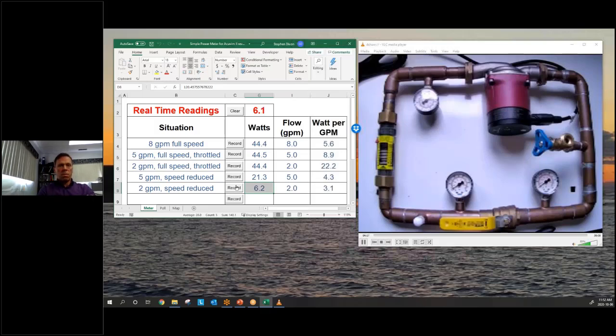Now, if you need pressure, we have to be careful here. If we need pressure, we may not be able to go that low. So in an open system where pressure is required, or if we have valves in the system, we have to be a little careful that we don't drop below it. There are going to be limits to how much we can reduce speed, because the throttling in the system may be a result of zone valves and different things within the system. I've simplified the situation here, but I think it shows quite clearly that by applying speed control, we can see a dramatic drop in power.